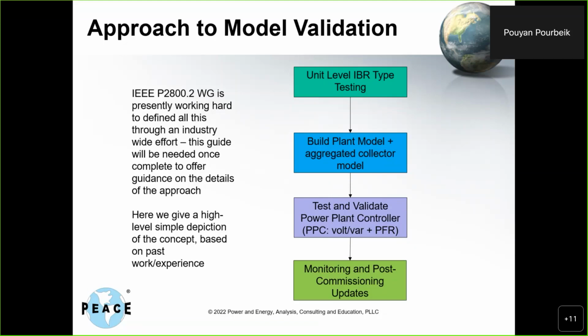It's a piecewise process, but it covers all the bases, because you can't test voltage ride-through in the plant - you're not going to put a three-phase fault at the POI and see plant ride-through. So you rely on unit-level type testing, building the plant model, and trusting that your unit-level models are accurate because you've tested those. If you build the aggregate and have evidence that the aggregation process works, you've got a good plant model at this second level. I can test that plant model to see if it rides through, and it's all good. Then if I want to verify the plant controller does what it would do in the field, I can test that in this purple box.